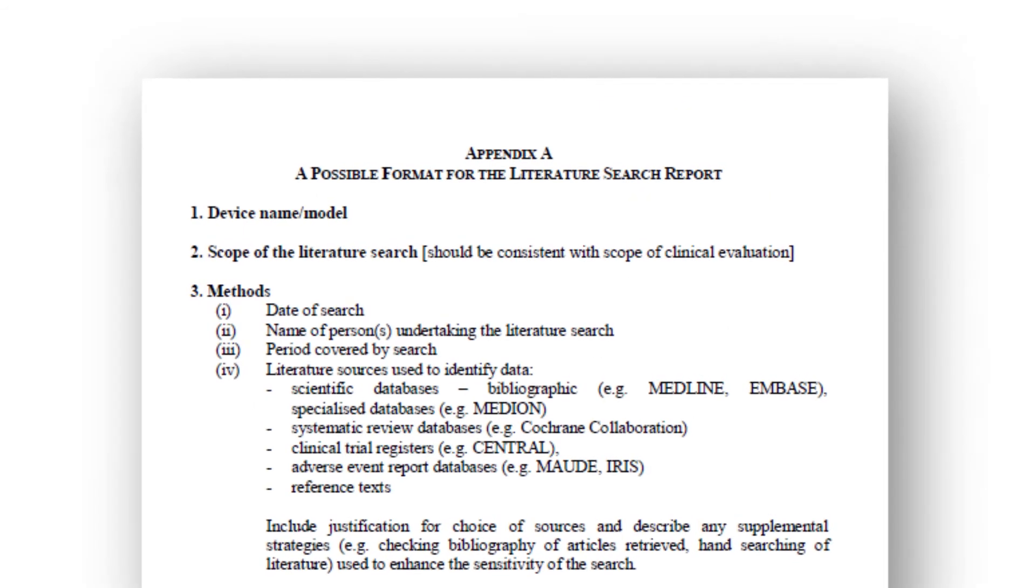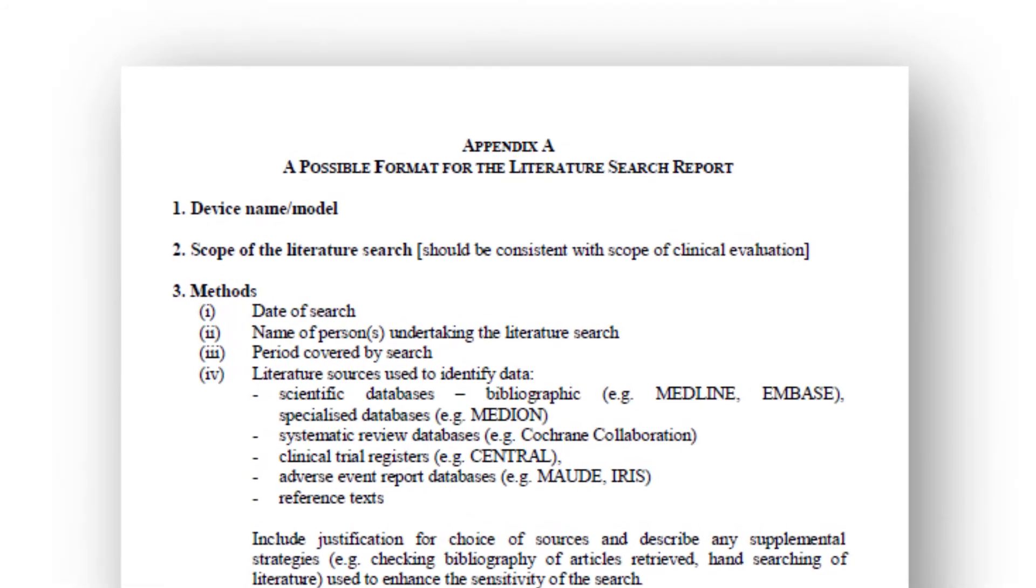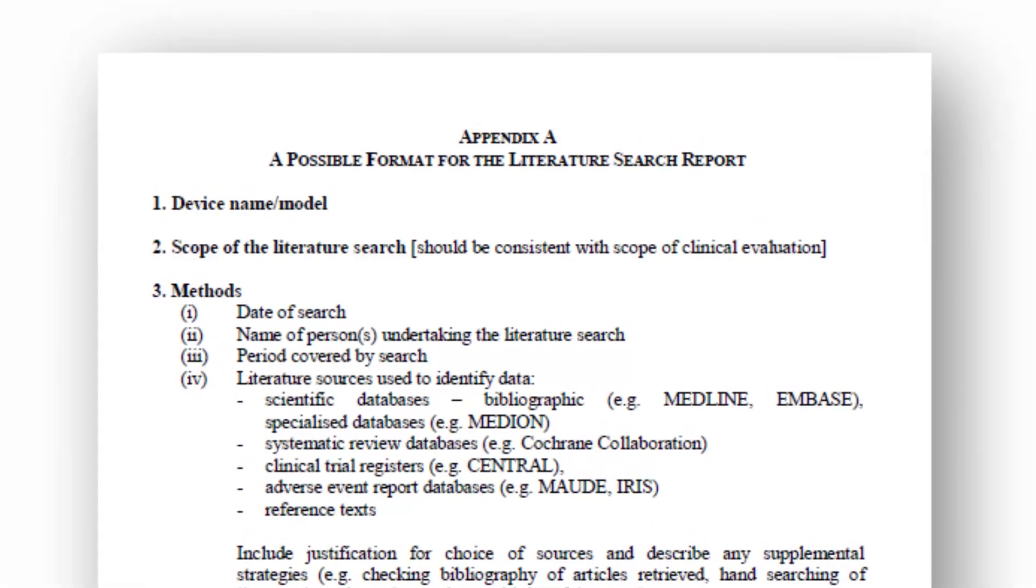The CER follows the format listed in Appendix A of the MedDev. You include the CER as part of the technical file that you submit to your notified body.